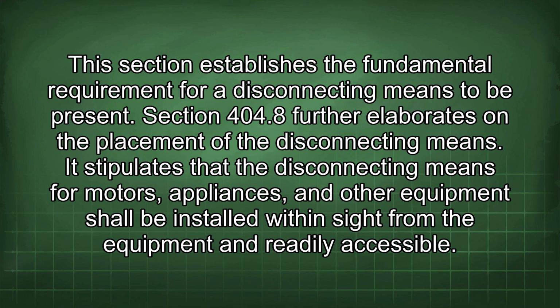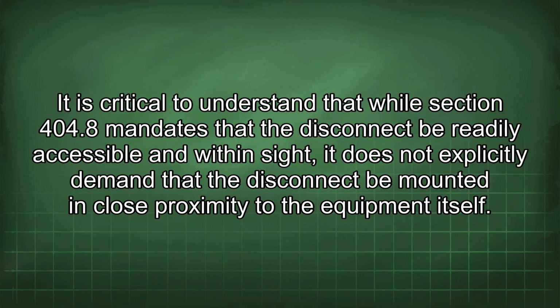Section 404.8 further elaborates on the placement of the disconnecting means. It stipulates that the disconnecting means for motors, appliances, and other equipment shall be installed within sight from the equipment and readily accessible. It is critical to understand that while Section 404.8 mandates that the disconnect be readily accessible and within sight, it does not explicitly demand that the disconnect be mounted in close proximity to the equipment itself.